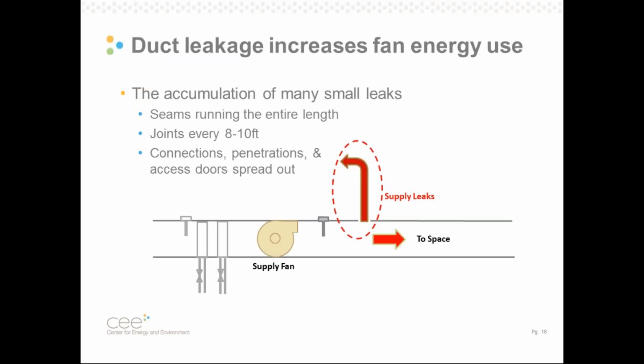So the main issue is that duct leakage increases fan energy. Here I've got this cartoon, which is some arbitrary supply fan in an air handler, and it's delivering air through ductwork into the space. I mentioned we have this accumulation of all these leaks. Air that leaks out of this duct system before it reaches the final diffusers obviously doesn't do its intended thing, which is to supply ventilation, heating, and cooling to the space. Thus, the fan energy that we use to move that air is completely wasted.